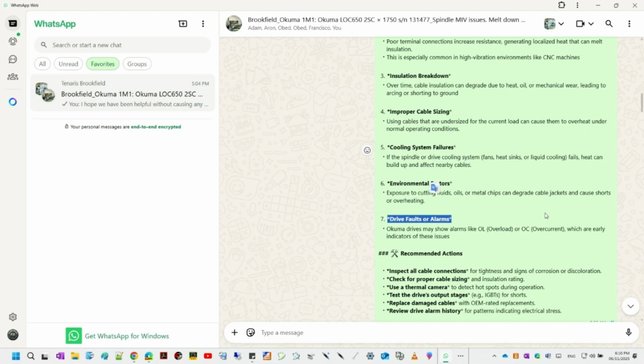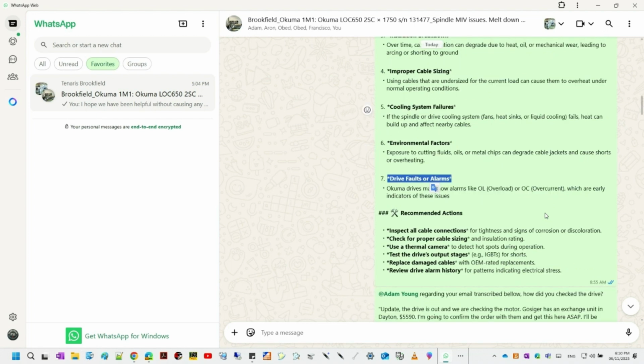They also did a motor insulation check, the Megger test. That's critical to rule out a motor fault causing the issue. And how did that look? It came back really good, actually. 550 gigaohms between each lead and ground. So that effectively ruled out a winding fault in the motor as the primary cause of the cable melting. The motor was healthy. Okay, so motor's good. That points back to the drive or the connection.